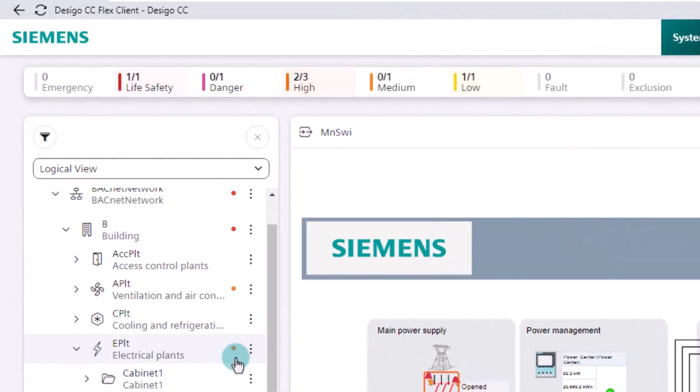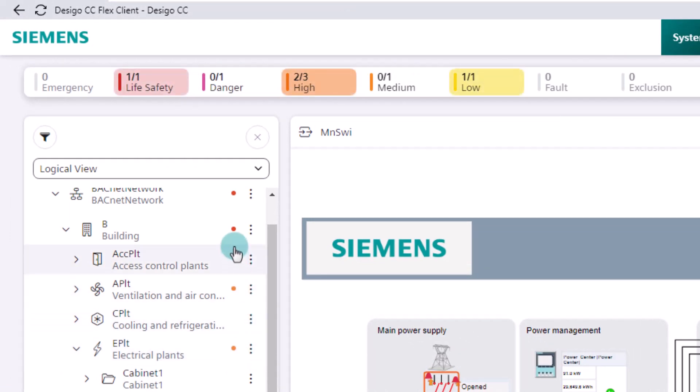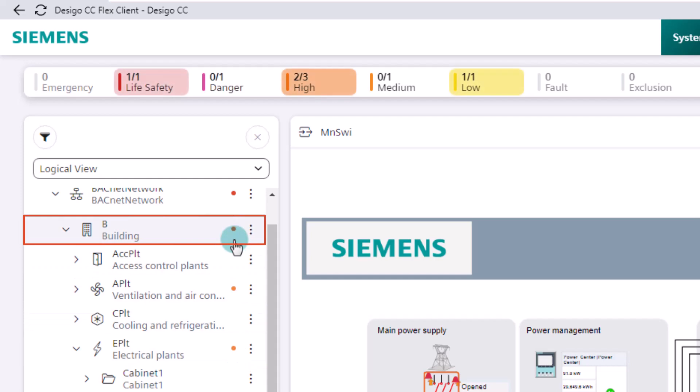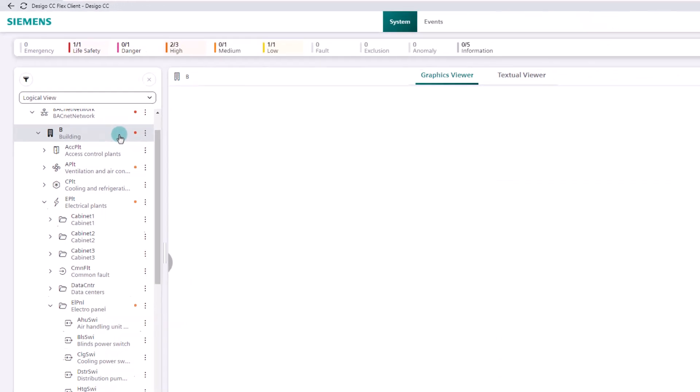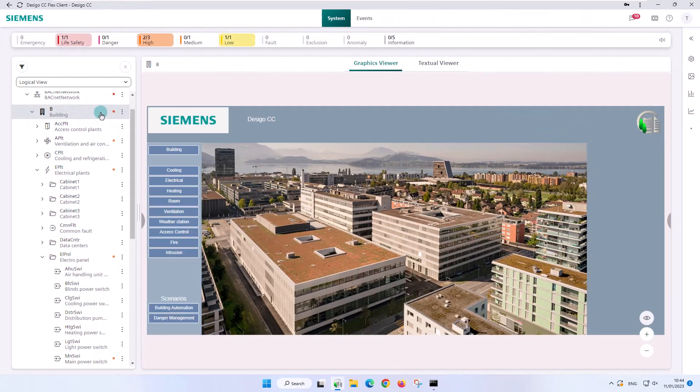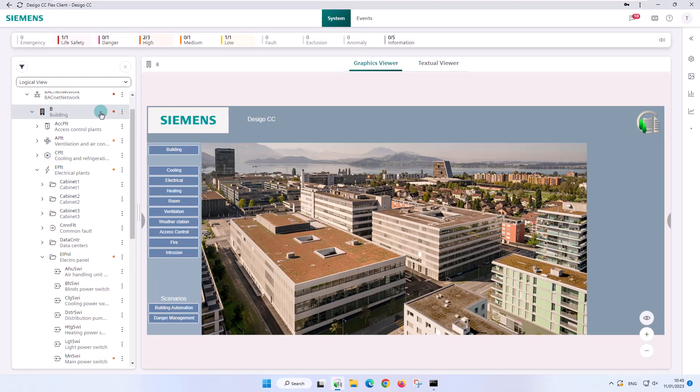In a parent object, the color with the highest priority of the child objects is always displayed. This can be seen in our example with the hierarchical object building. The color category was taken from the fire safety plant, the highest priority.